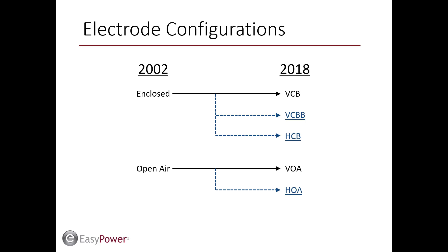Electrode configurations: the previous version of the arc flash model was based on enclosed and open air equipment types, with testing of electrodes in a vertical orientation. New testing showed that orientation is an important factor for incident energy estimation and should be considered. Therefore, the enclosed and open air types were further defined by their electrode orientation. Enclosed from the 2002 standard is now defined into three different orientations: VCB, VCBB, and HCB. Open air is now defined into two different orientations: VOA and HOA.